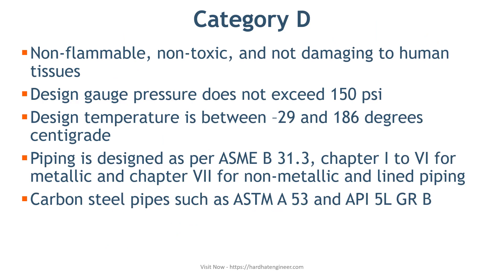The first is Category D fluid service. Any fluid service that fulfills all the requirements stated here is categorized as Category D. The first condition is that the fluid handled is non-flammable, non-toxic, and non-damaging to human tissue. The second condition is design pressure — for this service, the design gauge pressure does not exceed 150 psi.